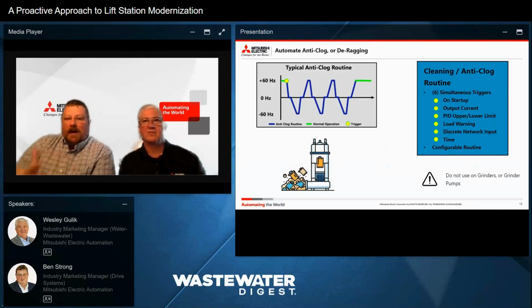Here's a typical anti-clog or deragging routine. I think the most important thing I've seen with this is you have to know if your pump can be reversed. If not, that doesn't mean you can't use an anti-clog routine. It just means don't reverse your pump. And you have to understand mechanical systems to implement it. There are systems you shouldn't implement an anti-clog routine. There are pumps you shouldn't rotate backwards.